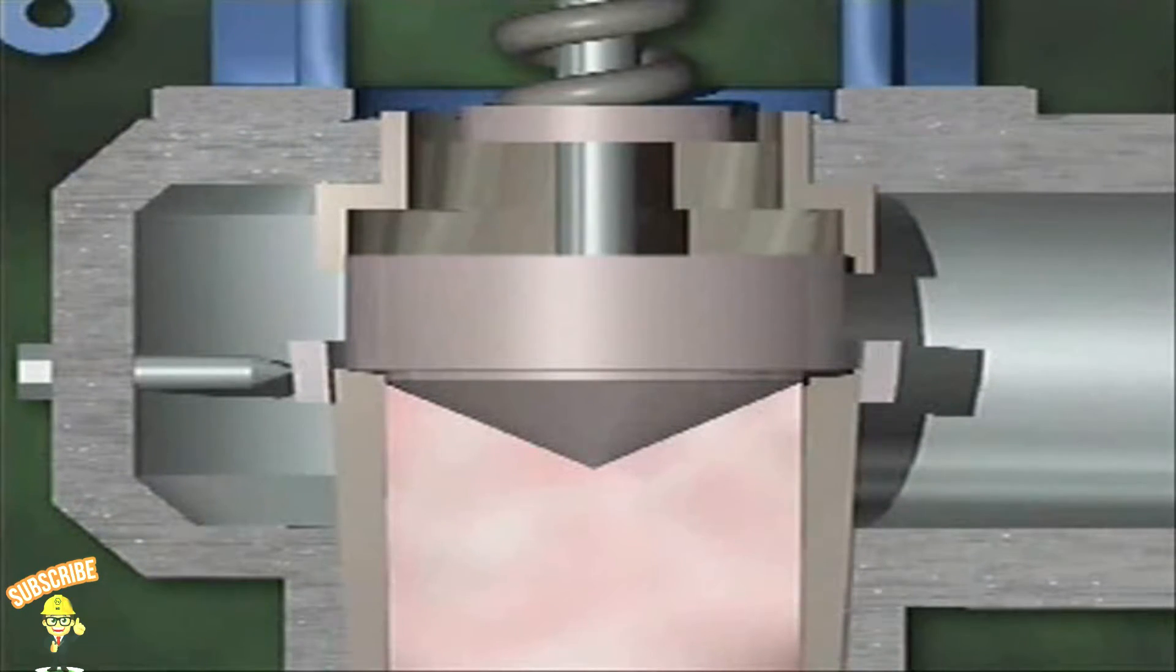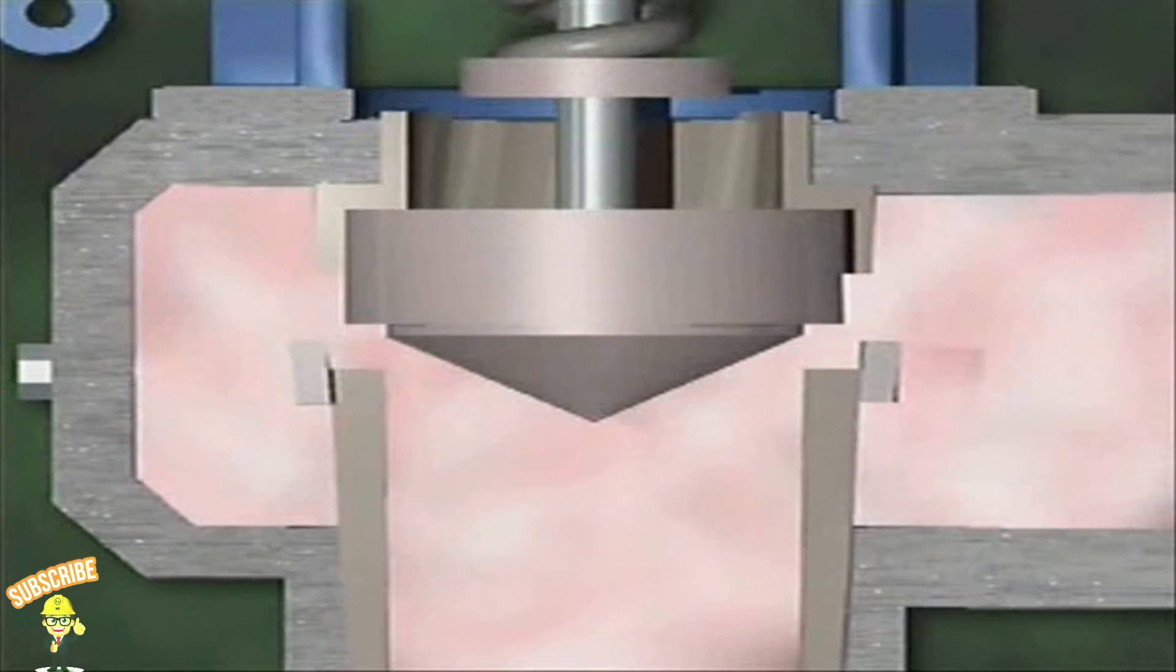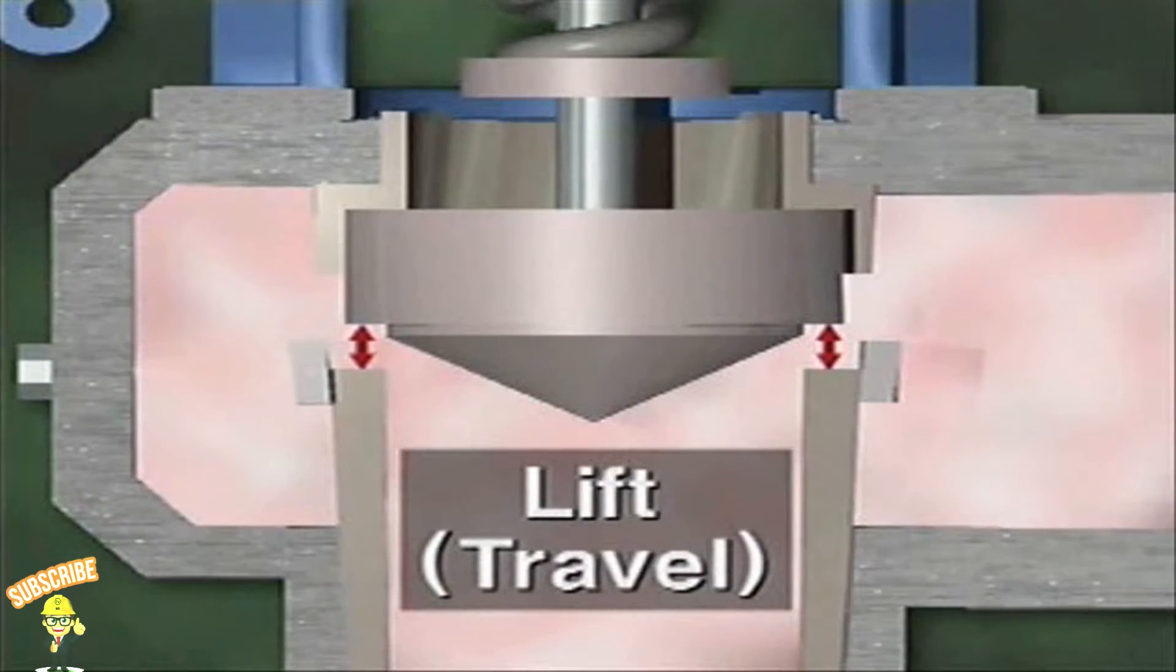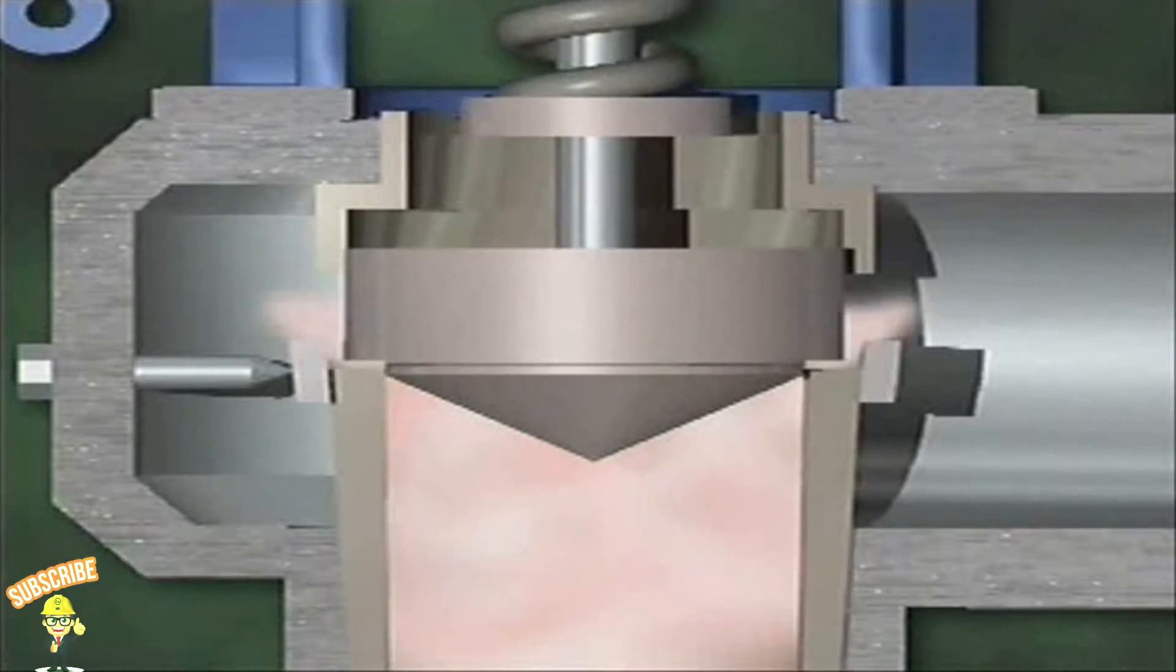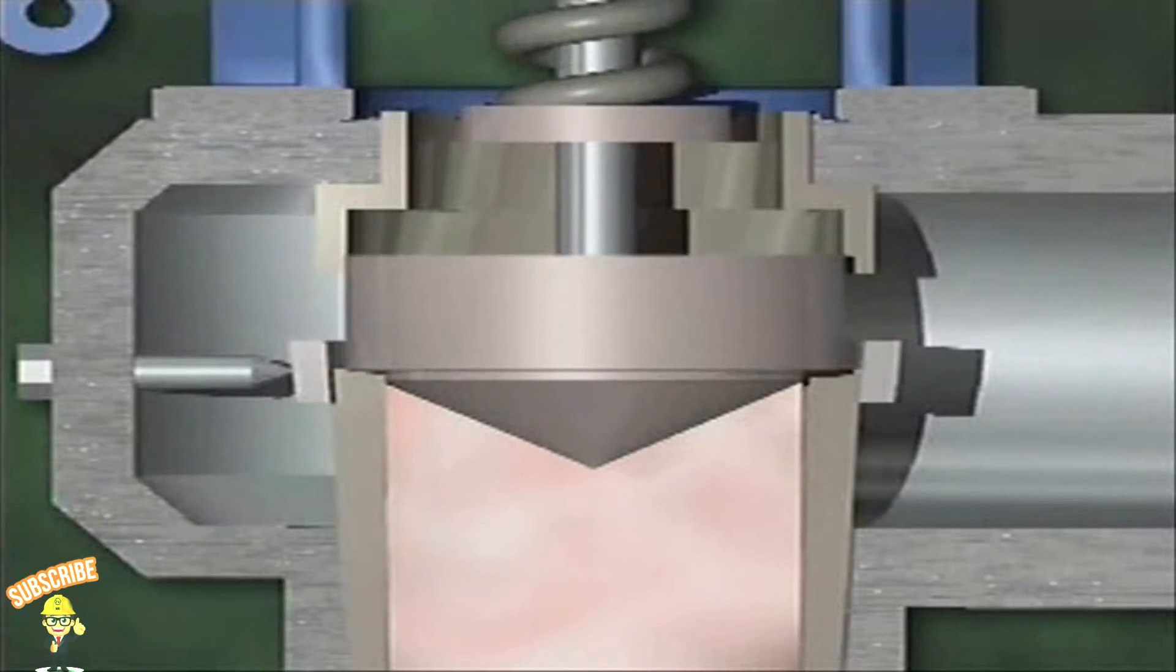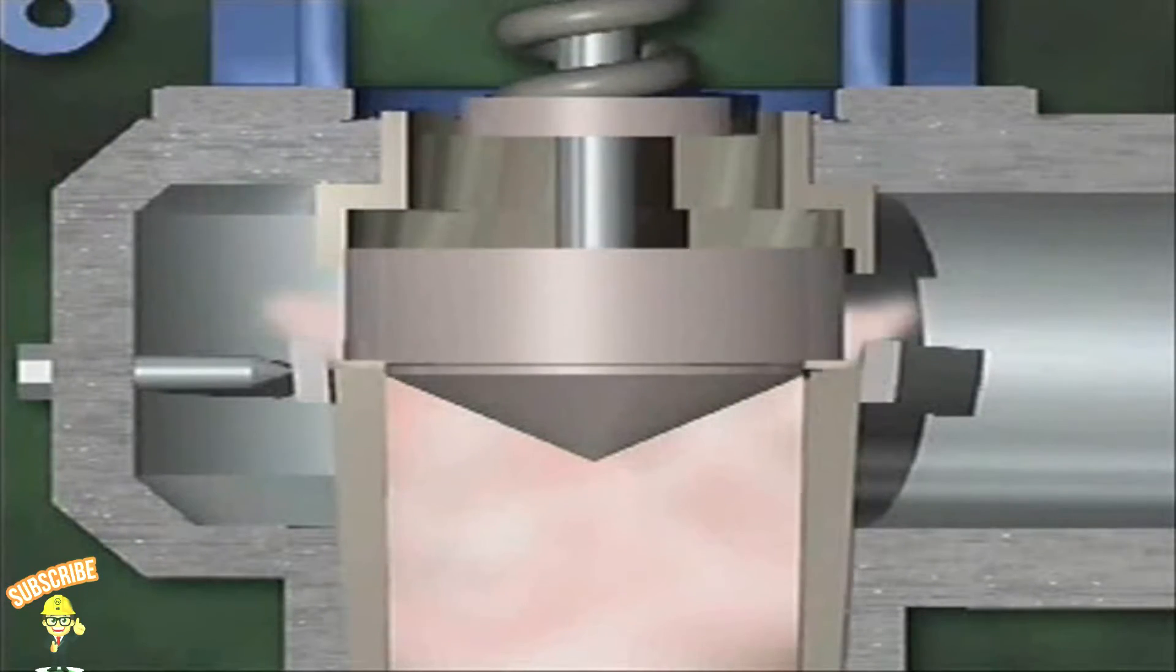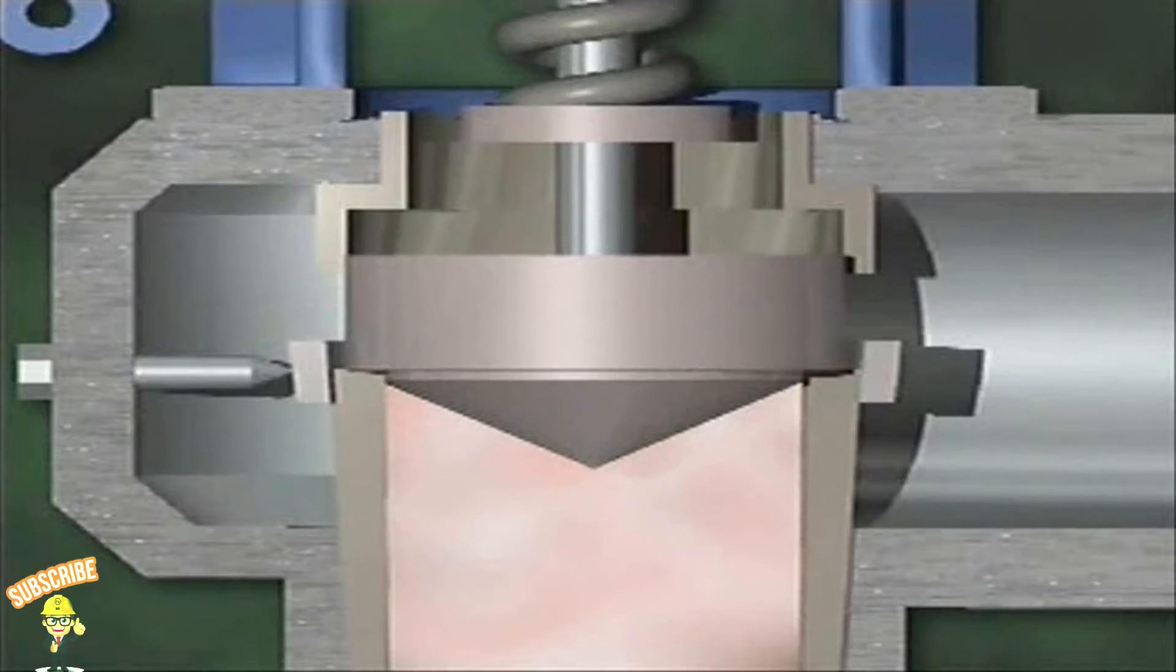The distance that a valve disc moves from the closed position to the fully open position is referred to as the valve's lift or travel. Adequate blowdown helps prevent a condition called chattering. If there's no difference between a valve's popping pressure and its seating pressure, the valve disc will jump up and down on its seat until pressure either increases enough to pop the valve open again or decreases enough to keep it closed. This condition is called chattering because of the sound that the disc makes as it moves up and down.